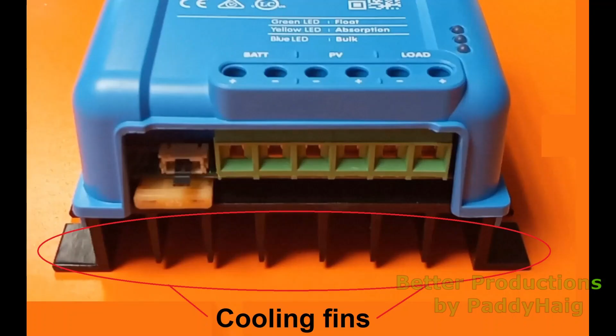Most MPPT solar controllers will burn off that excess power in a controlled way using a heatsink, usually metal fins on the device. The MPPT shouldn't ever get overly hot, though it can handle some excess amperage and will warm up a little - that's okay. Still, it's best to get an MPPT controller rated pretty close to your solar panel output, if not higher.